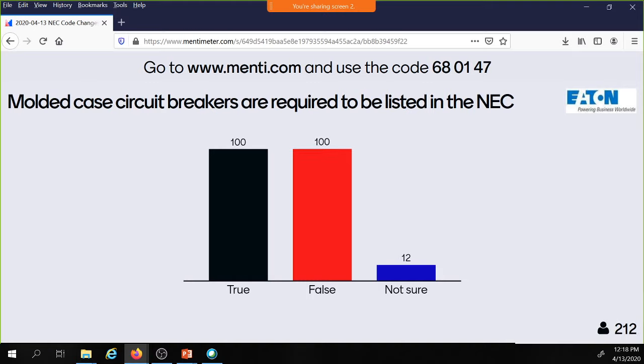Now, I know there are some jurisdictions that will require this, and as far as the authority having jurisdiction, anytime you have a product that's installed, the electrical inspector, the authority having jurisdiction, will have to approve that. We make their life easier by putting that little sticker on there for the listing mark. If they can look and see that it was evaluated and listed to a third-party standard, that makes their life a lot easier. If it's not listed to a third-party standard, they've got to really look at the instructions, make the considerations and figure out how they're going to feel comfortable making that call that it is okay for that installation. So they will normally look for that listing mark.